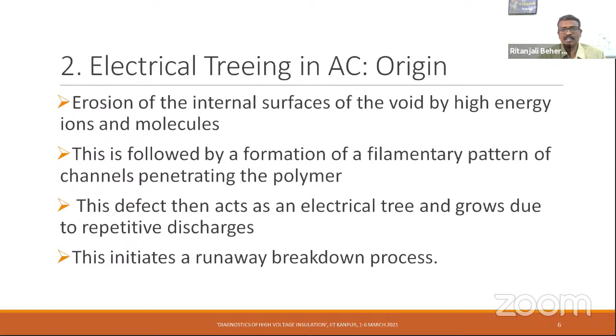This defect can act as an electrical tree and grows due to repetitive discharges, leading to the breakdown process. In the treeing, enormous amounts of discharges take place, depending upon the field condition and the nature of the material. This intense partial discharge activity in the tree tubules accelerates the tree channels, increases their diameter, and increases the tree structure as such. Finally, the tree structure reaches the ground electrode and causes a catastrophic failure.